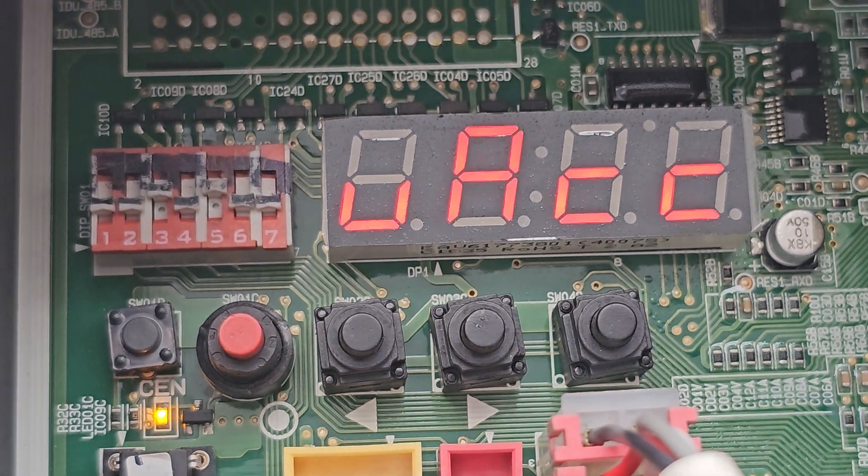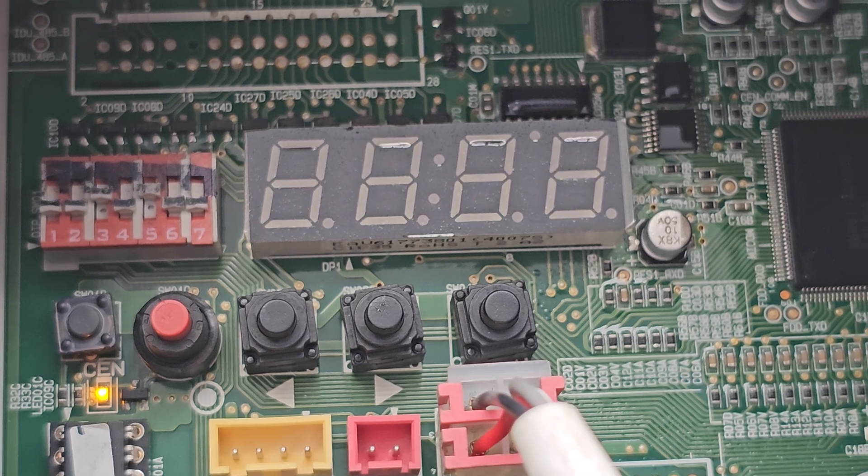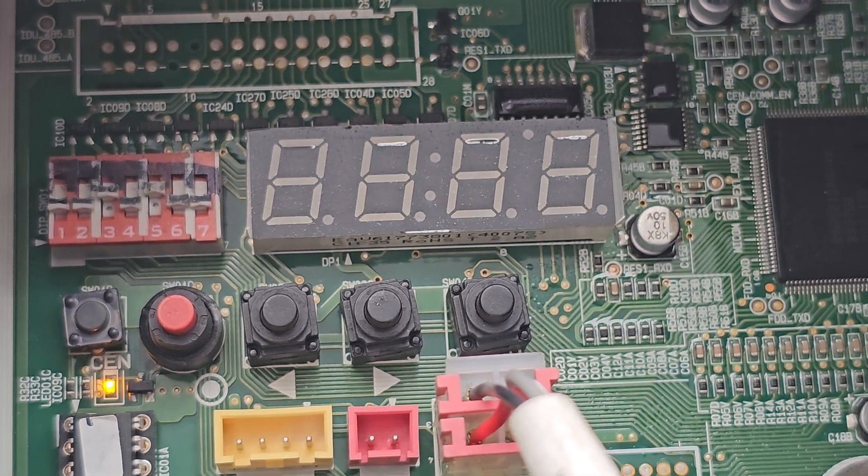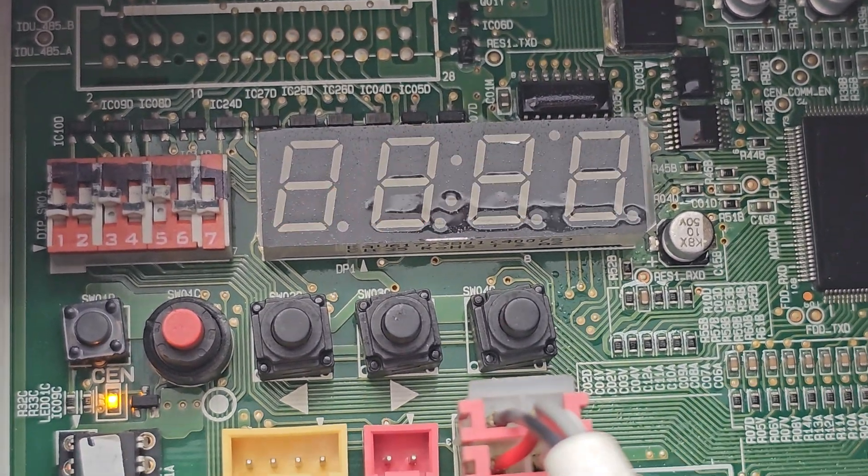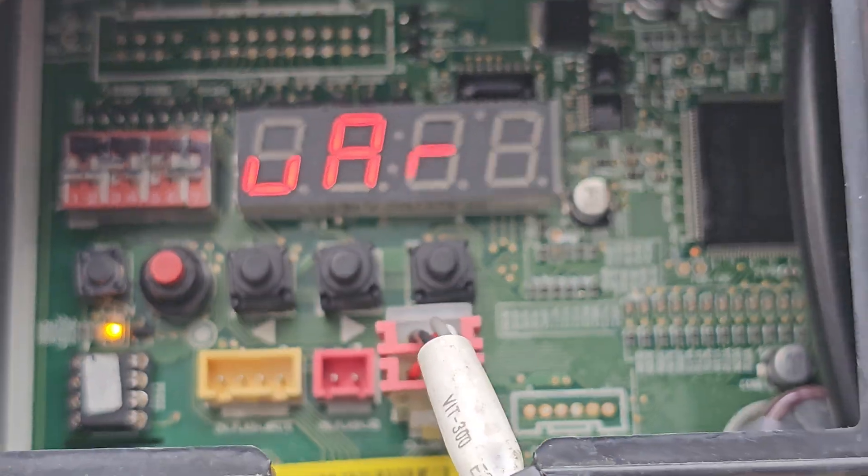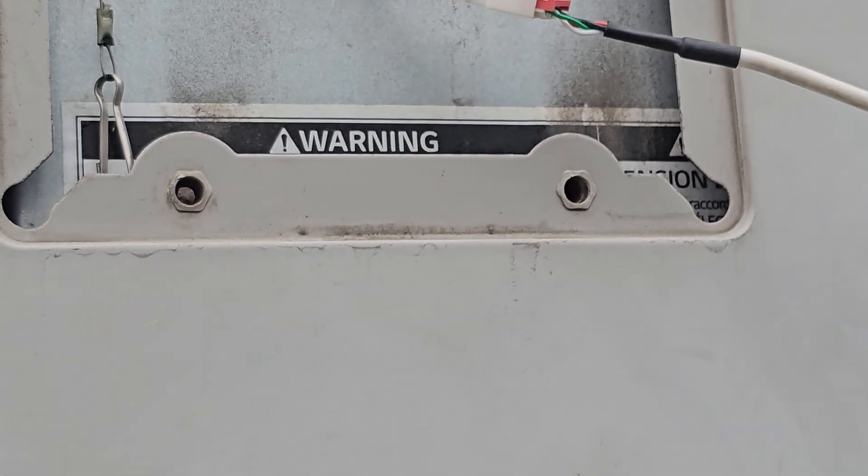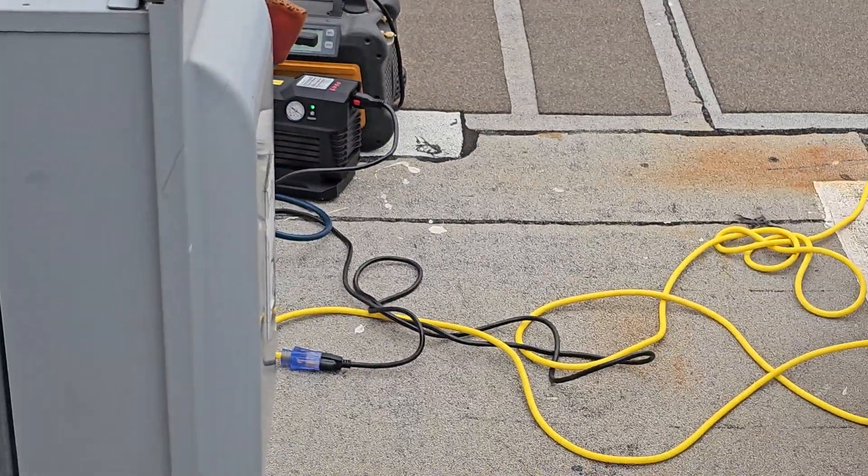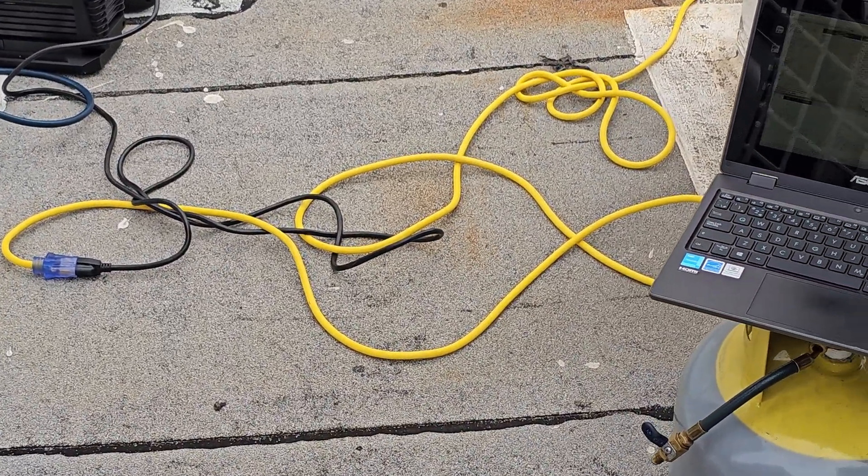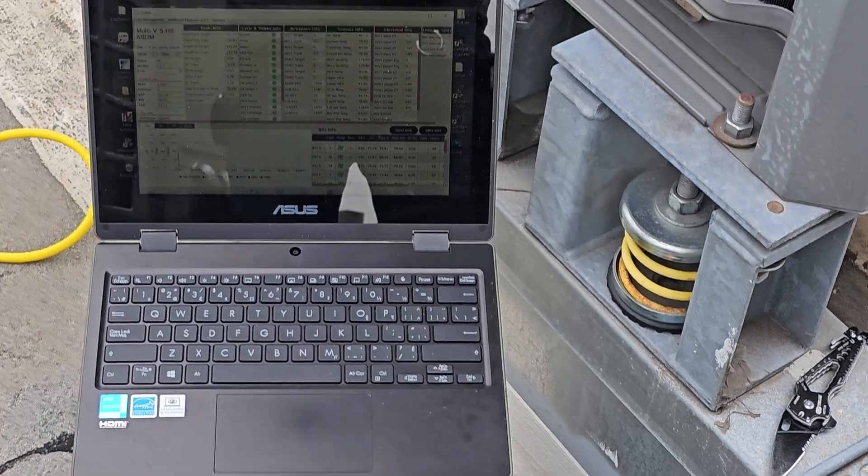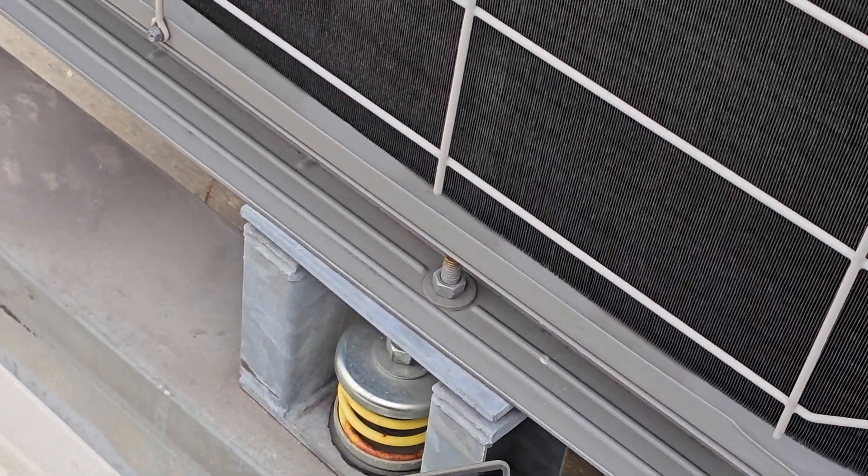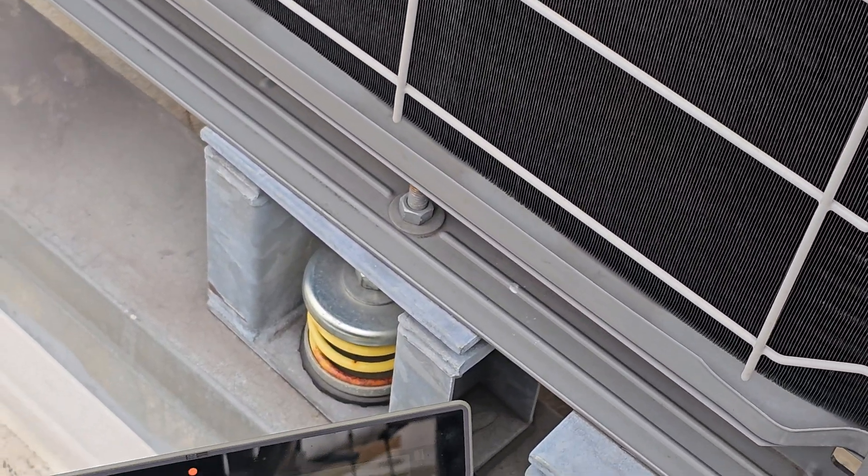It's important to note: the reason why it wasn't going into vacuum mode is simply because one of my IDUs was calling for cooling. Make sure you shut off all of your IDUs before you attempt to put it in vacuum mode, otherwise you'll be sitting there pressing that button forever.